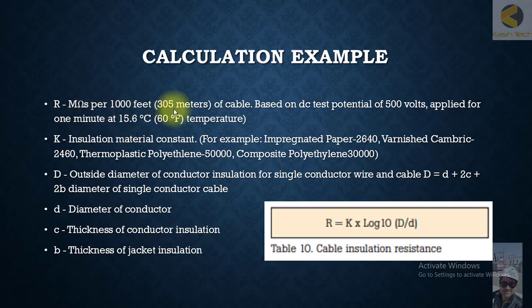Let's see where R is in the formula, megaohms per 1000 feet (305 meters) of cable based on DC test potential of 500 volts supplied for one minute at 15.6 degrees centigrade or 60 degrees Fahrenheit temperature.